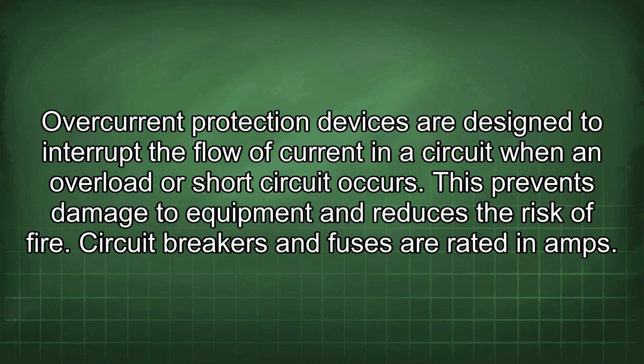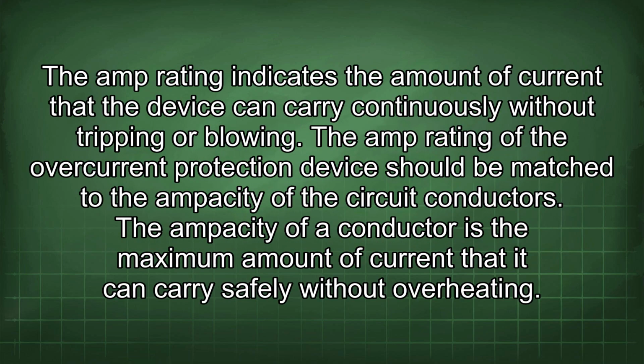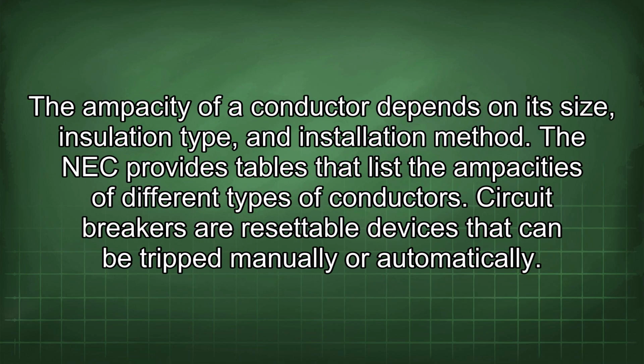Circuit breakers and fuses are rated in amps. The amp rating indicates the amount of current that the device can carry continuously without tripping or blowing. The amp rating of the overcurrent protection device should be matched to the ampacity of the circuit conductors. The ampacity of a conductor is the maximum amount of current that it can carry safely without overheating. The ampacity of a conductor depends on its size, insulation type, and installation method. The NEC provides tables that list the ampacities of different types of conductors.